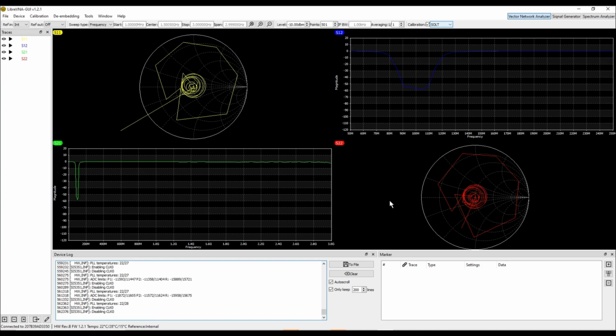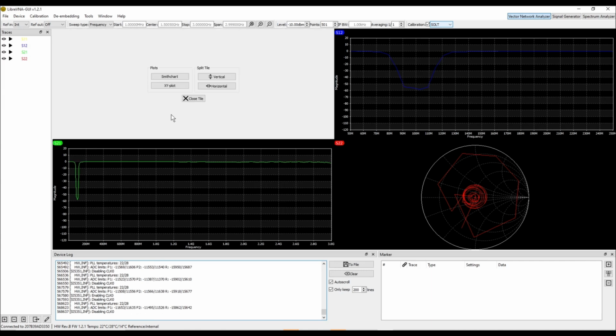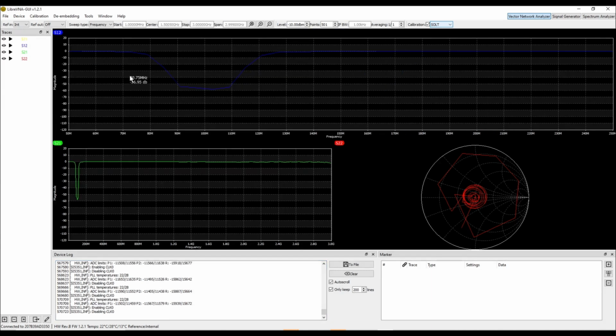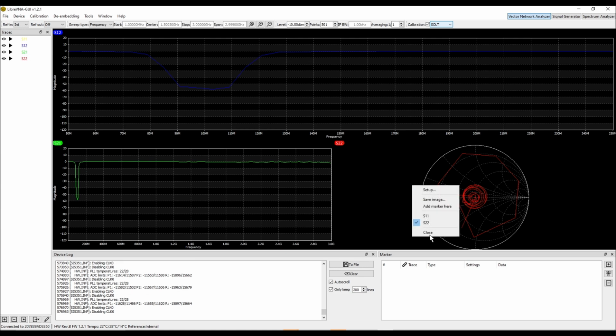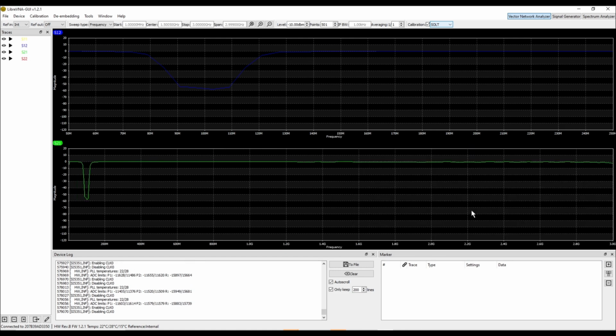So we have a couple of different charts and graphs here. I want to clean two of these up. So what I can do is come here and go close and then close tile, and then I get a larger S21 measurement on my screen. I'm going to do the same thing with this one. I'm going to close that one. And this is an S21, so this is coming out of the first port into the second, and it's measuring attenuation.